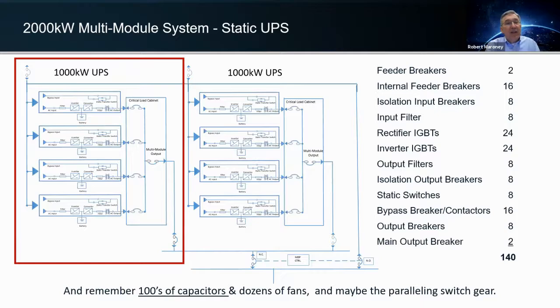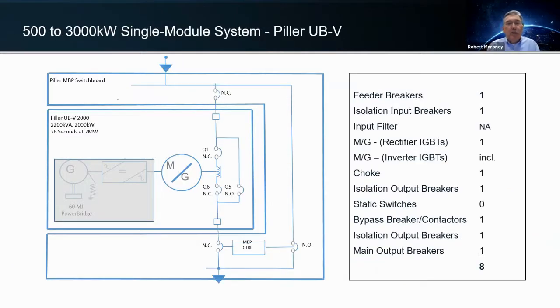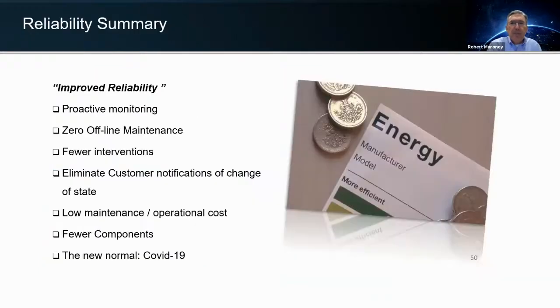So how does that relate? If you look at a Piller rotary UPS single module system, and this could be a 675, a 1,000, or 2,000, doesn't matter, you're looking at about 8 comparable components on the system. We feel that this is indicative of the reliability differential that you saw in my MTBF. And in neither system did we count stored energy, be it batteries or flywheel. We're just talking about the architecture of the UPS.